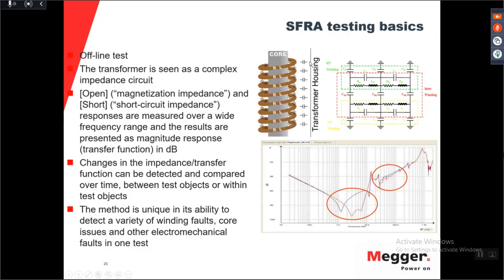If I have a problem in my inductive circuit, you usually see it in the lower frequency. If I have some winding displacement or problems in my winding, you see that in the middle of the curve, in the mid-frequency range. And then you have the shorter, the small changes. Any change that happens in this circuit will be seen in this measurement. So you will see almost any type of problem or any electromechanical fault in just one single test. But remember that you actually need to have a fingerprint, something to compare with.